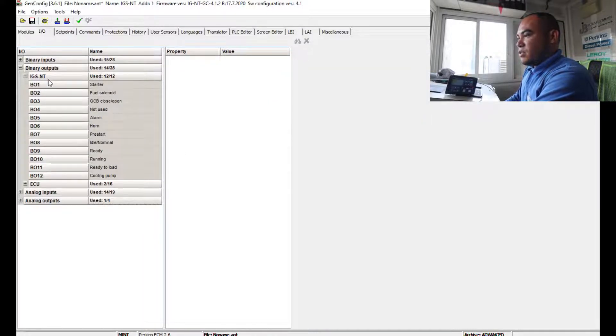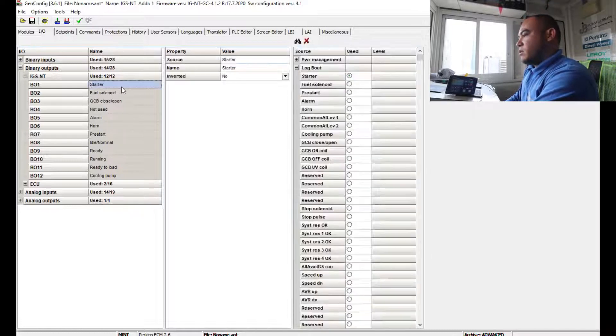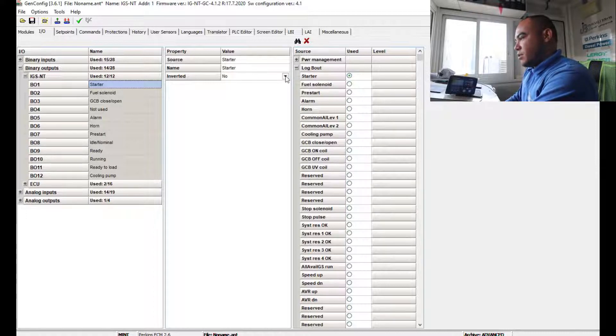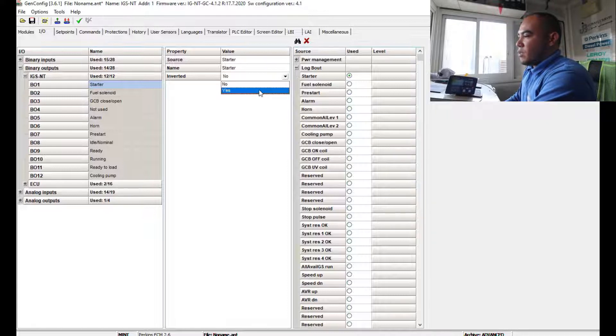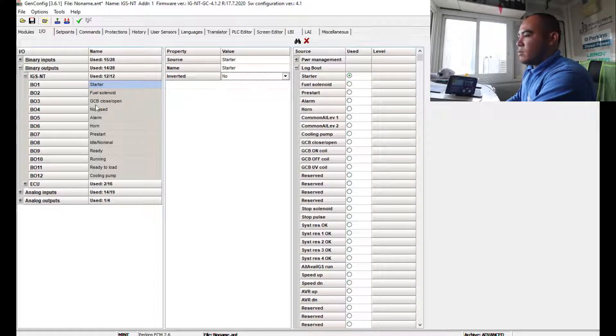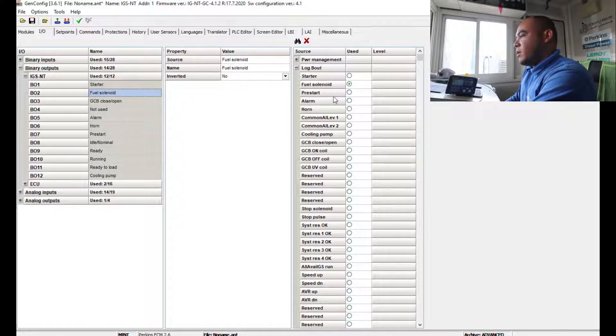For binary output configuration in the IGS-NT, you can designate outputs for Starter, Fuel Solenoid, GCB Close/Open, and more. Click the output you want to assign — for example, select Starter and assign it. Invert on an output means it changes the output polarity. For the Fuel Solenoid, click and select the appropriate function from the list, and the available selections will pop up.